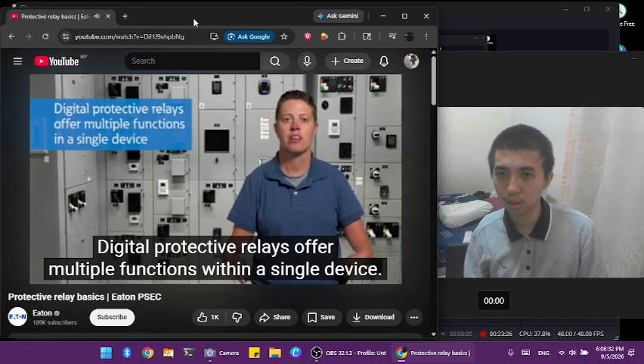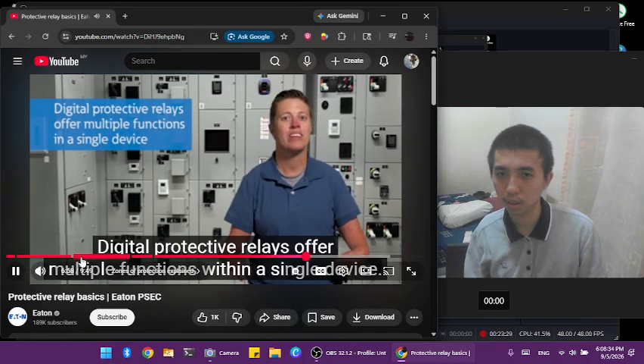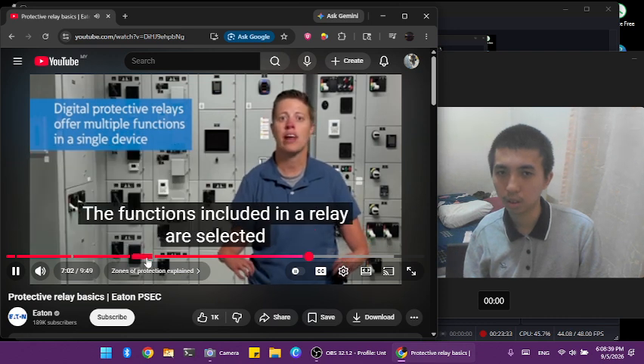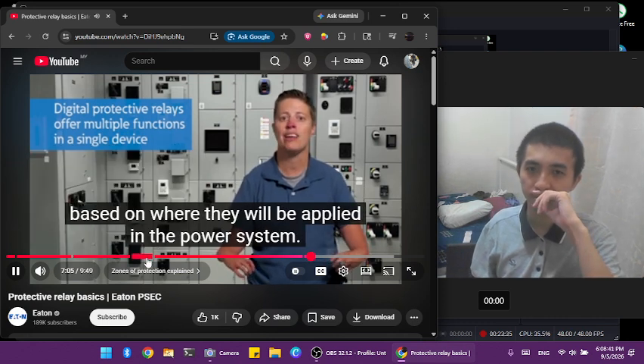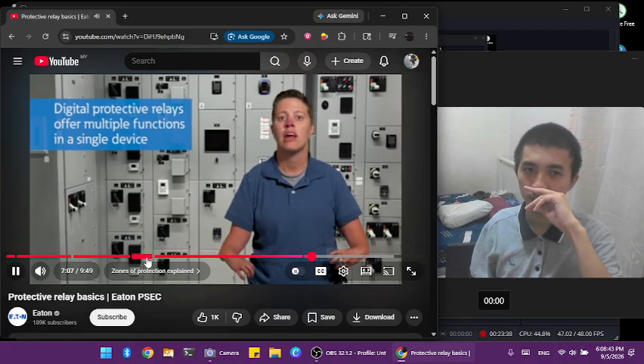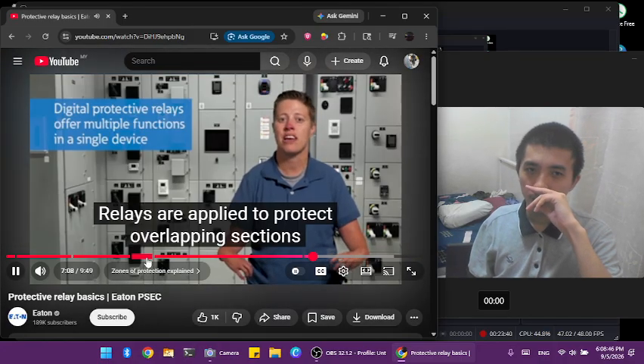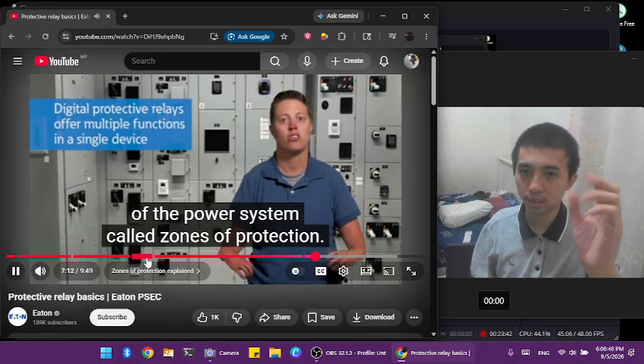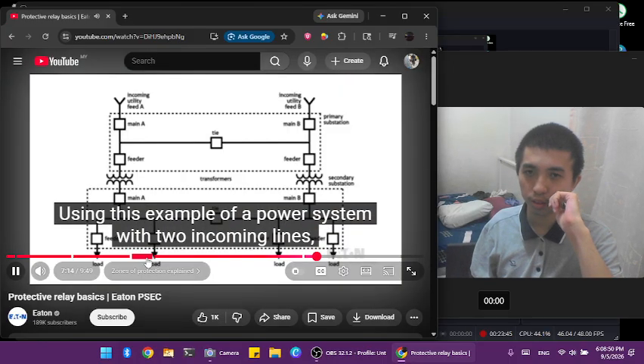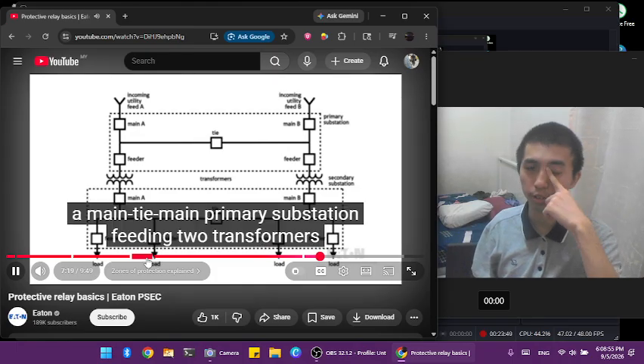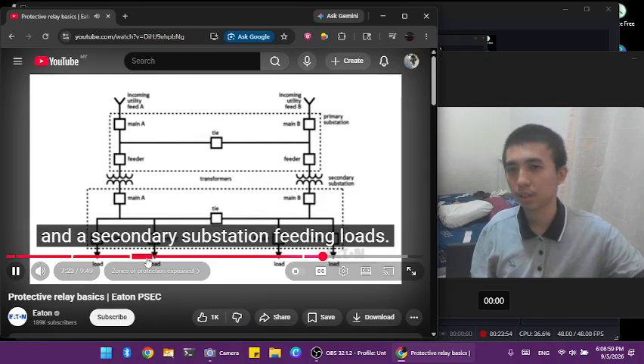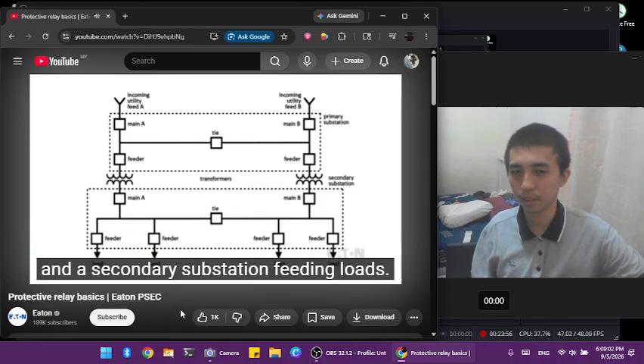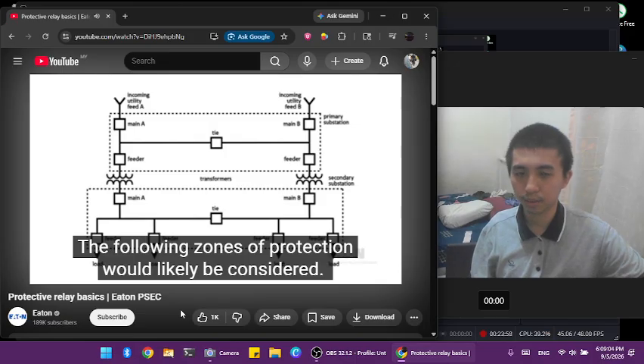Digital protective relays offer multiple functions within a single device. The functions included in a relay are selected based on where they will be applied in the power system. Relays are applied to protect overlapping sections of the power system called zones of protection. Using this example of a power system with two incoming lines, a main-tie-main primary substation feeding two transformers, and a secondary substation feeding loads, the following zones of protection would likely be considered.